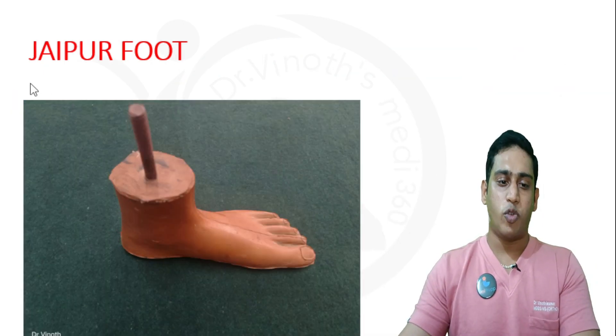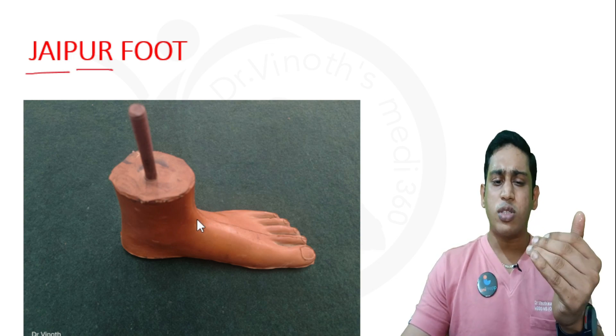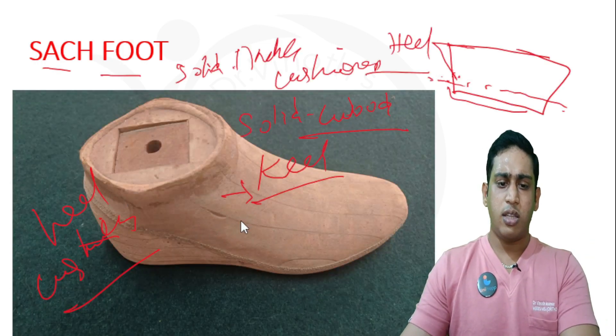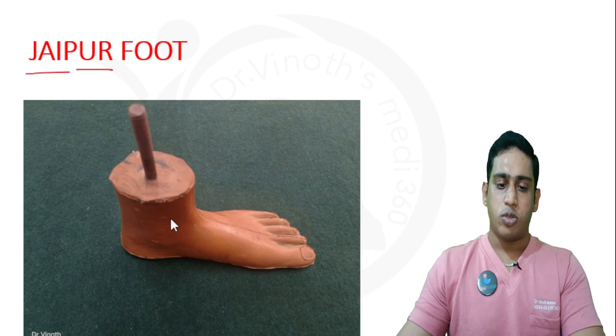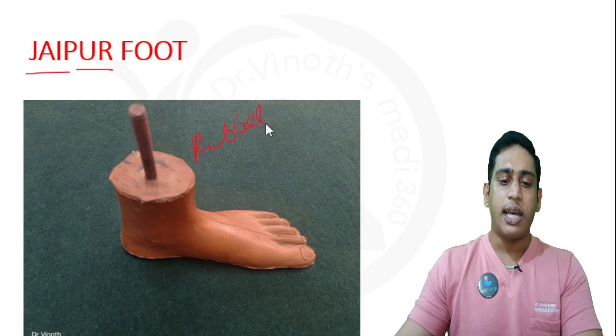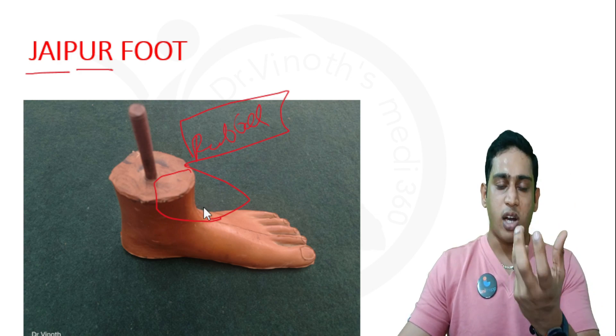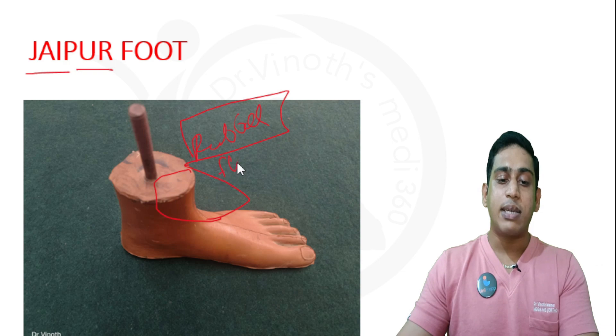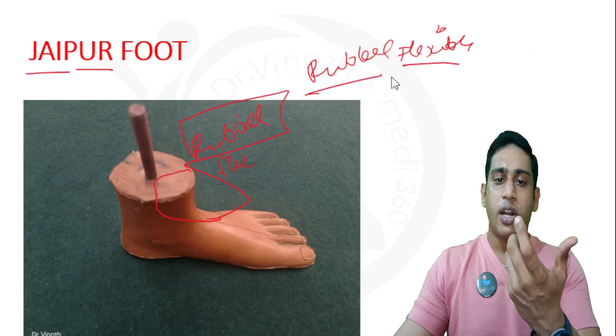The next one is called the Jaipur foot, since it is made in a medical college in Jaipur. At first look, the Jaipur foot looks somewhat similar to the actual limb — like a foot actually. It is made up of a rubberized or vulcanized rubber material. The keel part, which takes the shank of the prosthesis, is made up of a flexible rubber material.